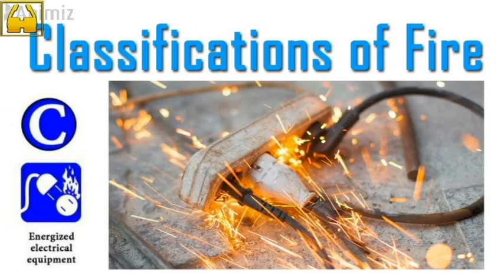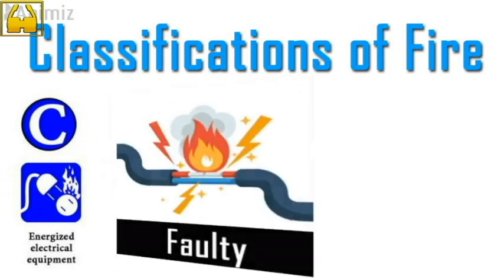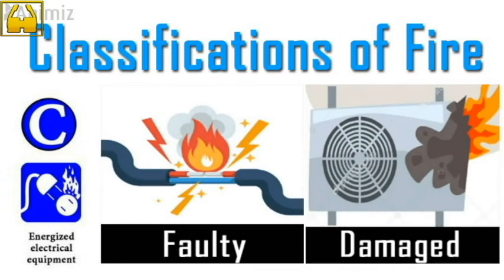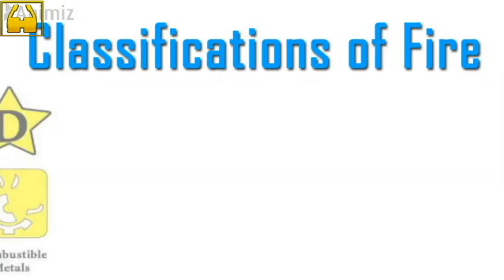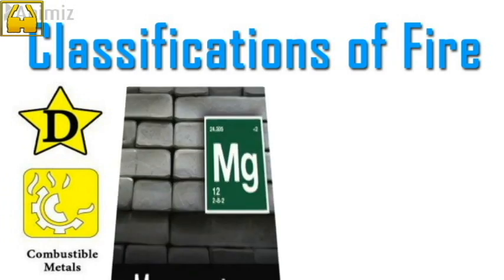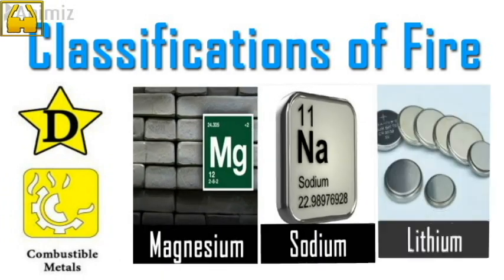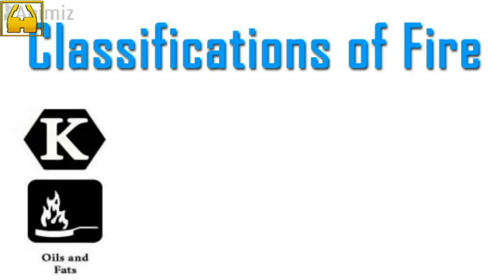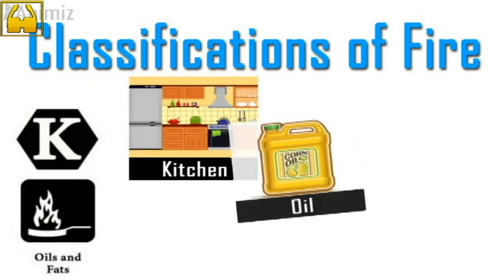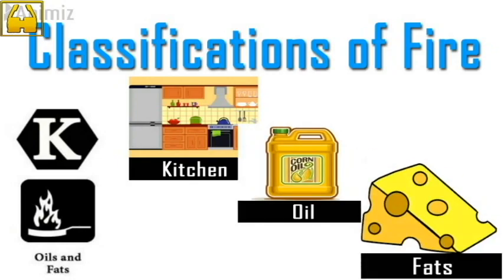Class C fires: these are related to electricity. Fires caused by faulty electrical equipment and damaged electrical appliances come under Class C fires. Class D fires: combustible metals come under this classification, such as magnesium, sodium and lithium. Class K fires: cooking-related materials such as oils and fats come under this classification.